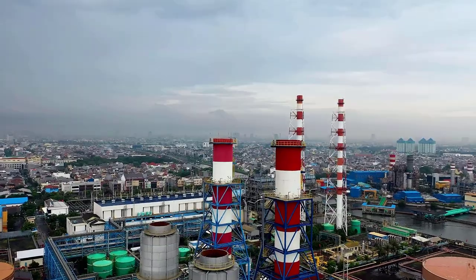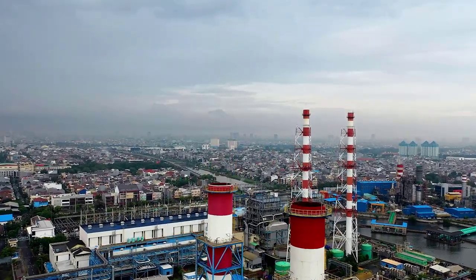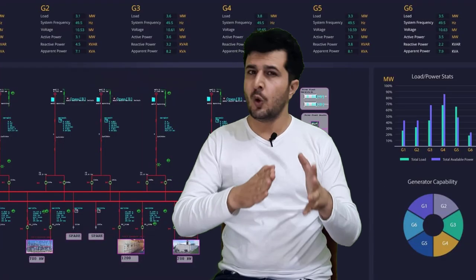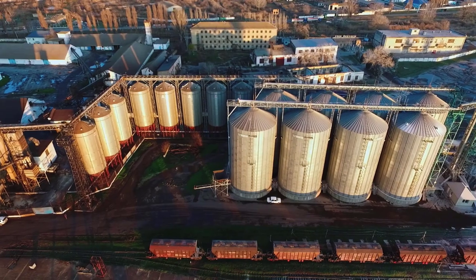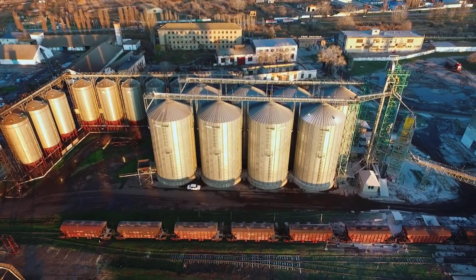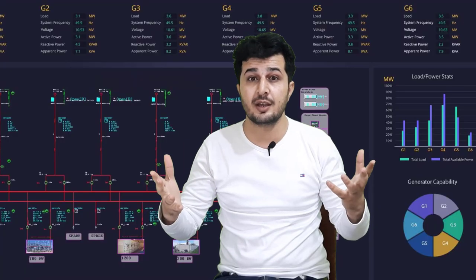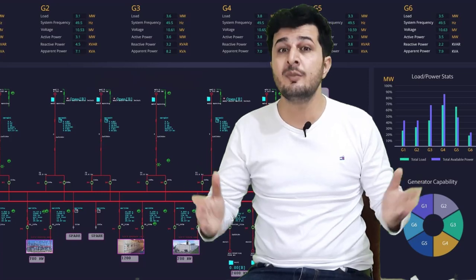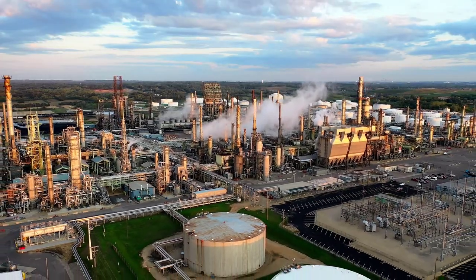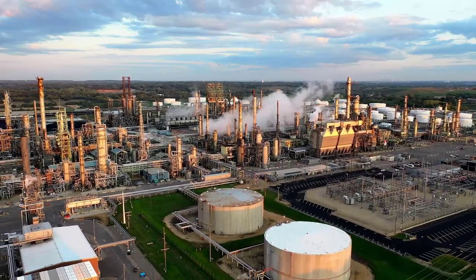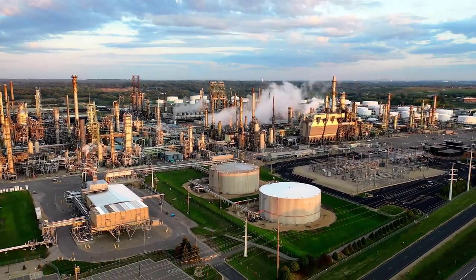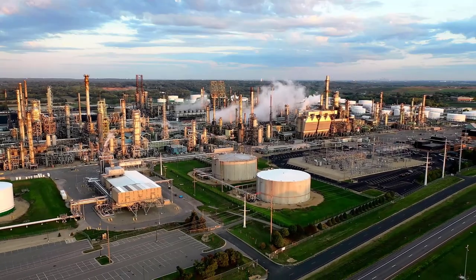Now let's talk about conditions where you would require a DCS system. For big production plants — fertilizer plants, chemical plants, cement plants, power plants — where you have a lot of analog I/Os to control the entire plant, it is always best to use DCS. It can also be used where process failure could cause a lot of damage. In a bigger plant with different process areas, each area in a DCS system has its own controller, with a main controller and a redundant controller.